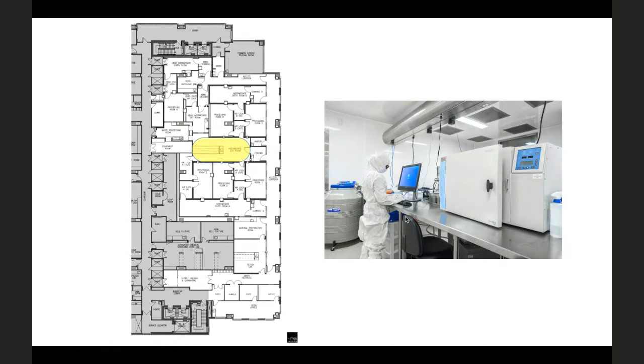So in this room, there's a waste pass-through back here in the corner. So that leads into a waste autoclave room where we deal with all of our waste. So we've got a separate flow for waste versus the product that would go out through the degown area. And then we also have our controlled rate freezer in this area and our liquid nitrogen storage. And our dewars for the source liquid nitrogen are on the other side of the wall. So the liquid nitrogen is piped into the clean rooms, but we don't have to manage cleaning a dewar to bring it in and out of the facility. It's just piped through the wall.